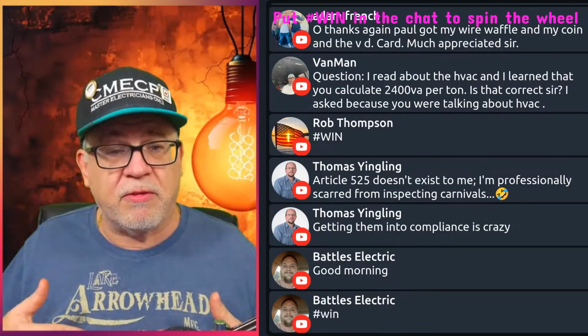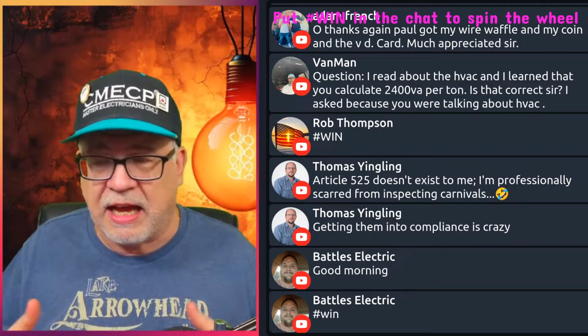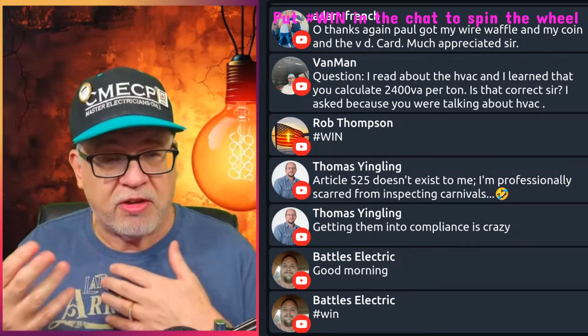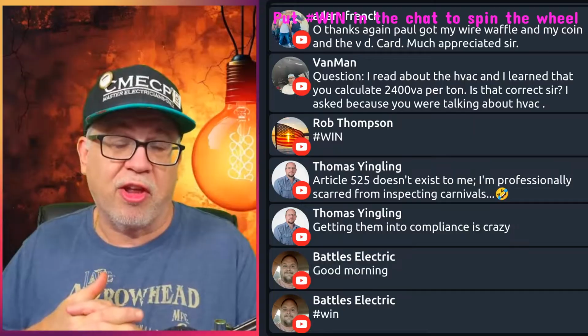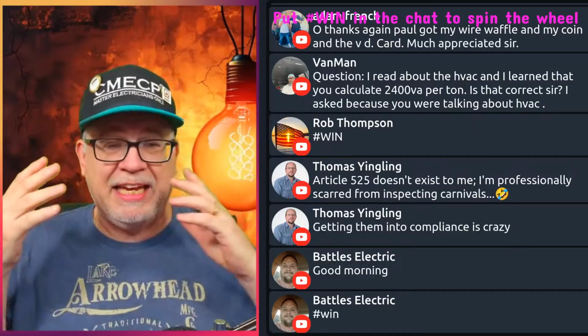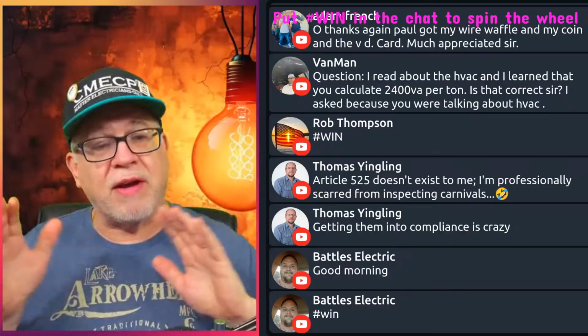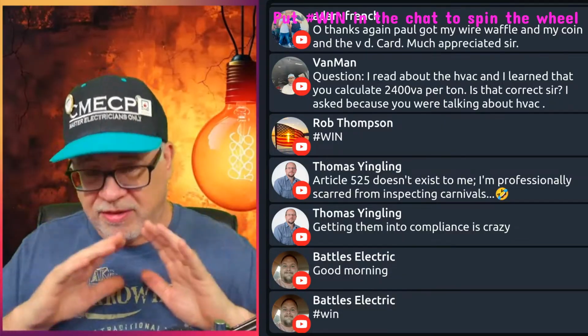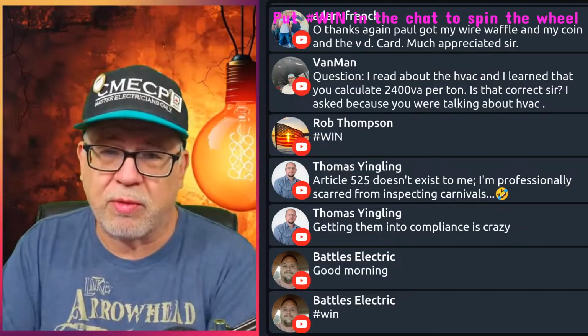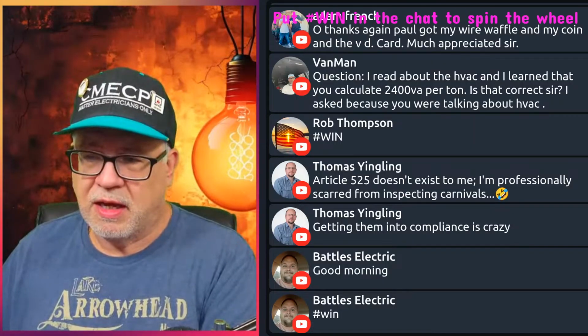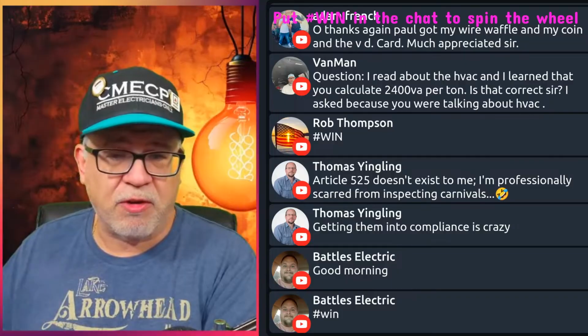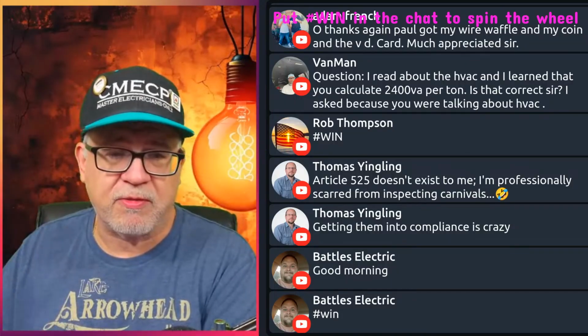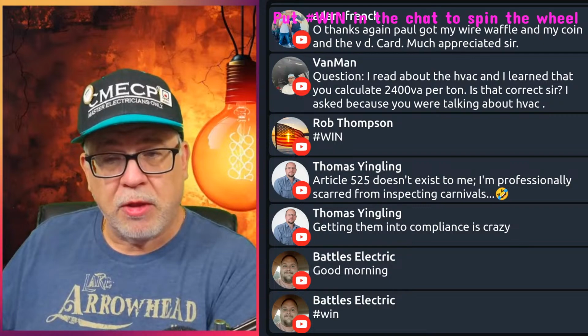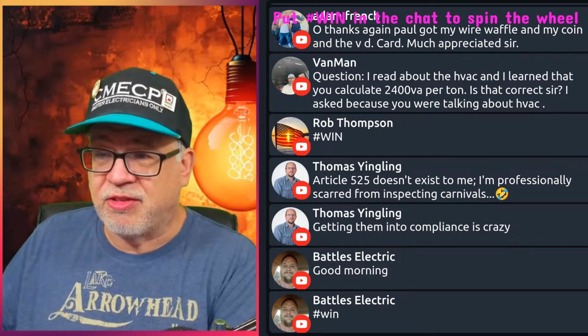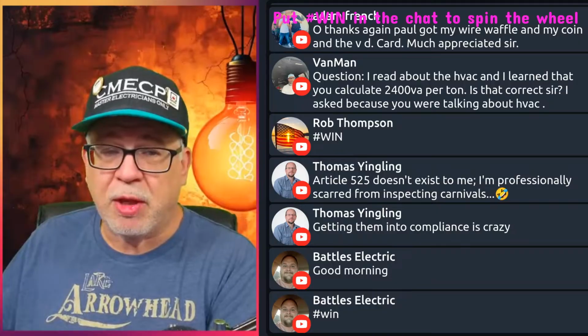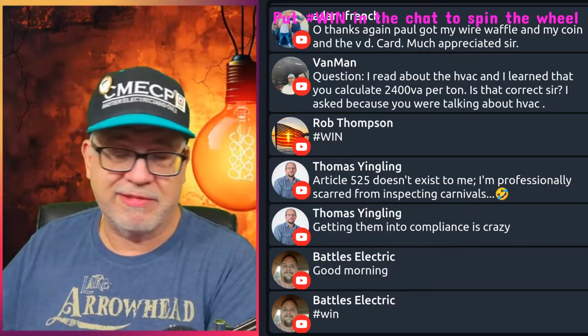Now, there are exceptions for this for DC fast charging, which doesn't have to have the GFCI. There's also an exception if it is bidirectional, where there's a company called Emporia, and there are other ones, that can actually use the EVSE to send power back in. So it's bidirectional, and obviously those don't have to have the GFCI protections. That's an exception to the rule. So moving forward in the 2026, GFCI protection will be required regardless. It just may be a GFCI versus an SP GFCI, with milliamp threshold differences and frequency differences. The one that you're going to install in your house is a standard. If it's a receptacle, the protection built into the EVSE is not going to cover it.